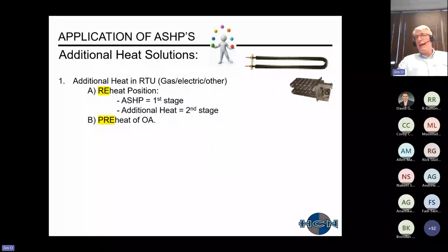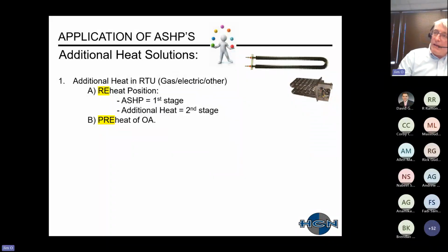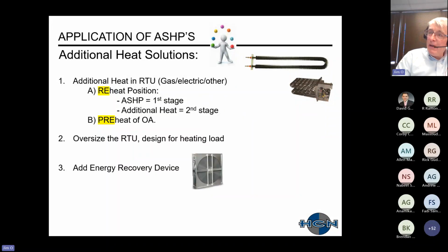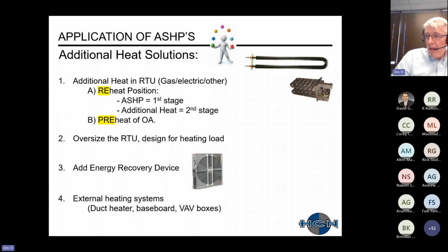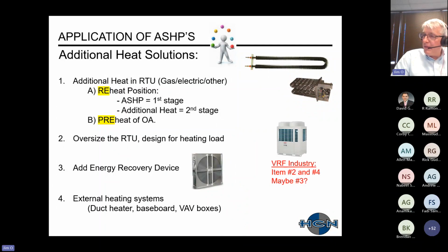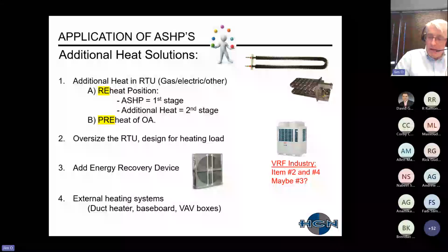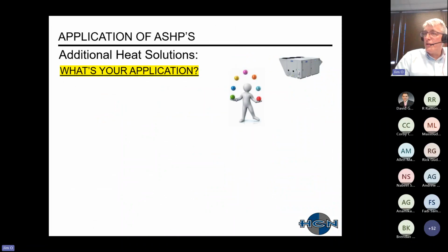So, additional heating solutions: you can add heat to the rooftop unit. You can position this in the reheat position where you'll have your air source heat pump as your first stage and your supplemental heat as your second. And then the other thing that's becoming a little bit more prevalent is to add a preheater just to the outside air. Other items, you can oversize your rooftop unit. Instead of designing traditionally for the cooling load, you can design it for the heating load. Can add an energy recovery device. This is showing just a wheel here. And then obviously external heating systems such as duct heaters, et cetera. And then just my observation is that item number 2 and number 4, if you work in VRF, you should be familiar with these concepts, and then maybe energy recovery units also for item number 3.